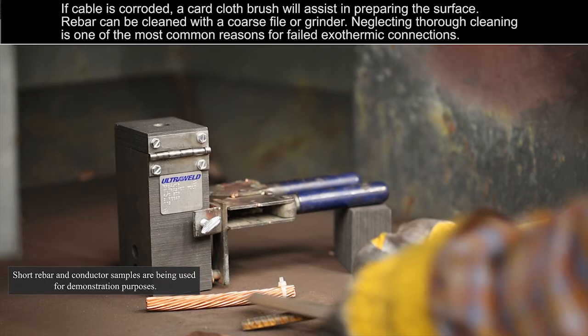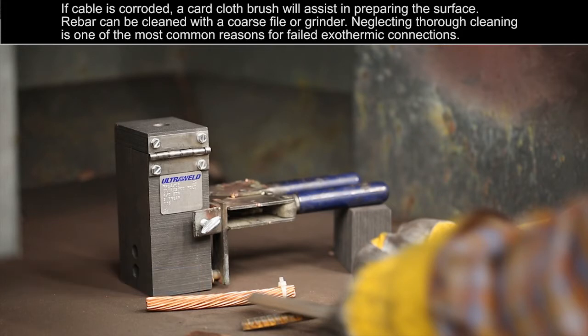If the cable is corroded, a card cloth brush will assist in preparing the surface. Rebar can be cleaned with a coarse file or grinder. Neglecting thorough cleaning is one of the most common reasons for failed exothermic connections.